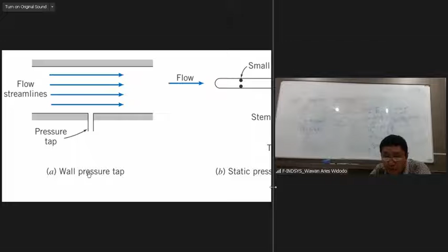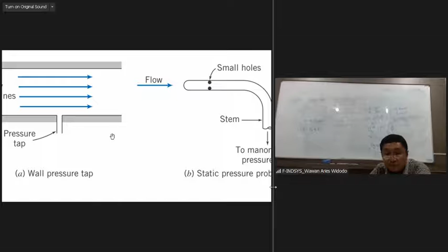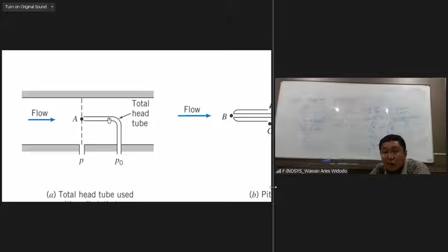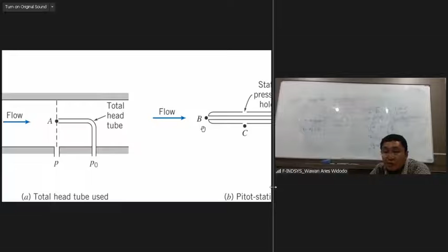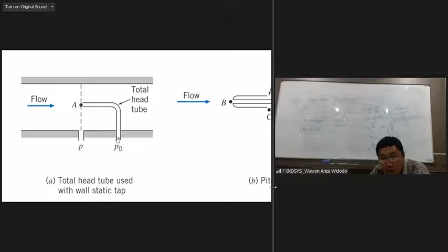Beside this hole in the pitot tube, this is in a duct or on a pipe, yeah, a circular duct or circular pipe, and then we install the hole here and connect it with a device to measure pressure, connected with a U-tube manometer. If you use a pitot-static tube, we can measure this. If it doesn't have the hole in this position, we can use the hole here. This is a different way to measure velocity inside the duct or inside the pipe. If the pitot-static tube is without a hole, we can use the tap here. This is the position of the tap to measure static pressure, and this one to measure stagnation pressure.